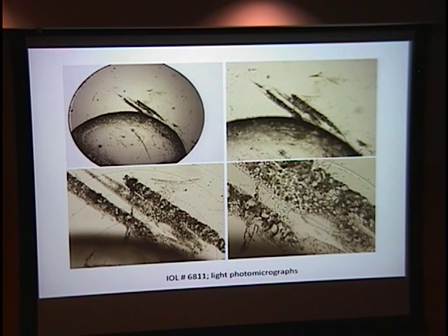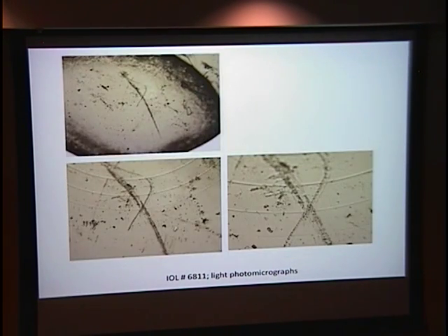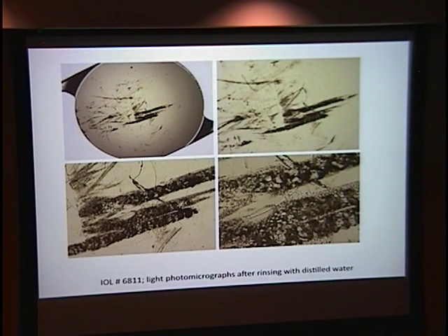No, they can't be retina. I think they gouged it when they did it. That was on the anterior surface. Seeing that stuff on there, I thought, what in the world, did they use a wire brush on that? I don't know, maybe when they were loading it, they scratched across it or something. And there you can see the multifocal aspect of it, but look at the number of scratches on this one. Look at this next one. Could it be the injector scraped on its way out? Yes, it could be the injector. It could be what instrument they grabbed it with. That happens all the time.